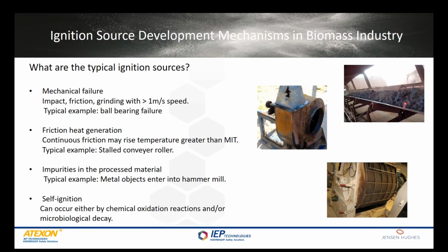And the last one, self-ignition, is the most difficult to understand because there are many factors affecting this phenomenon. For example, high humidity level or freshness of a biomass fuel leads to bigger risk of self-ignition. But the good thing is that this can be detected with multi-criteria gas detectors integrated to spark detection and extinguishing systems.